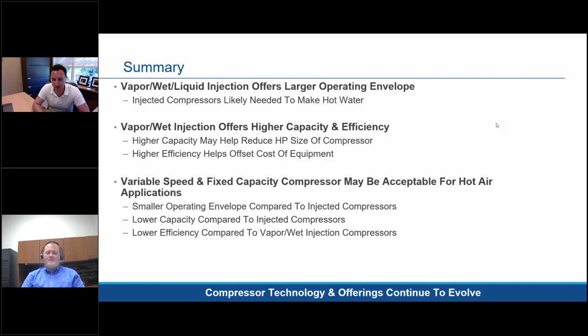Then this one's a little general. What typical COP increase do you see when you have vapor injection? A lot of it's going to depend on the specific operating condition. As you move farther up in the left side of the envelope, you're going to get a 20% increase. If you don't get in those low evap and high condensing temperatures, you might see a 10-15% increase. It really depends on where you're taking that COP reading at.